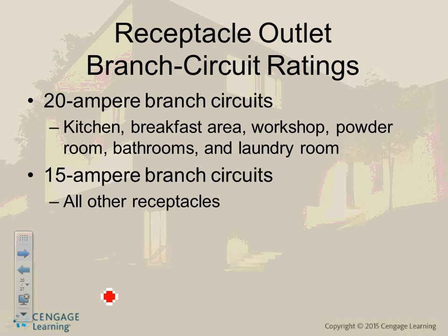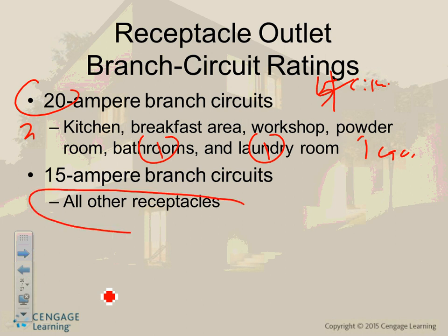Okay, so where do I need to have 20 amp circuits? I need two for the kitchen, I need one for the bathroom, I need one for the laundry and one for the garage. How many of them do we end up with? Five circuits. Actually, four 20 amp, and the one for the garage can be 15 or 20. All other receptacles will be what? 15 amp.